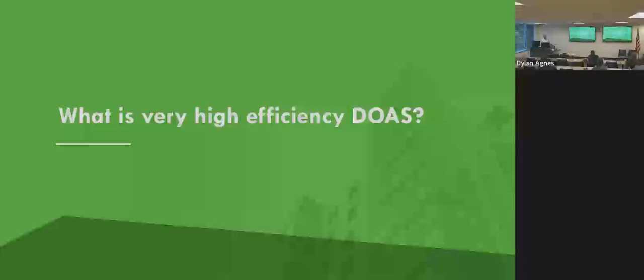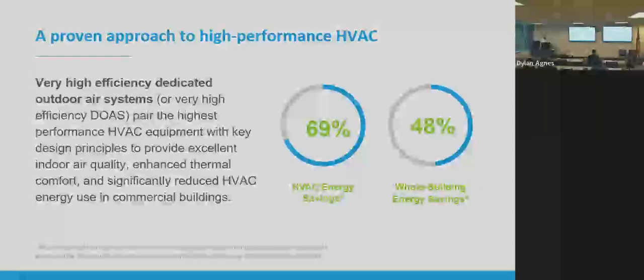All right. What is very high efficiency DOAS? Well, it's a commercial HVAC system that applies the heat pump technology. I'm talking about this because I have a ton of field data from this, 20-something sites where I have HVAC sub-meter data. Most of them have detailed annual energy models as well. So I have a lot of experience and a lot of data that I can share based off of this system. But today, I mostly want to talk about the heat pump performance, not the overall system. In general, across these 20-so projects, we saw almost 70% HVAC savings relative to the existing system with code minimum equipment. And then whole building savings, almost 50% savings. So basically we cut the building energy use in half across all these projects.